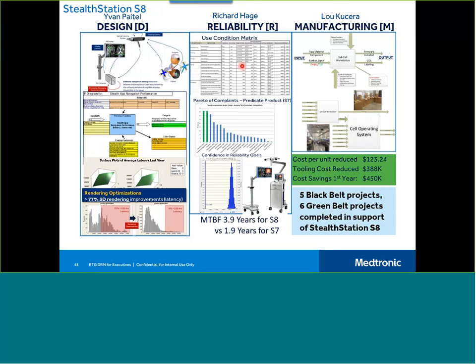On the reliability side, we did a use condition matrix and tried to look at all the ways this product could be used or misused or abused or whatever else, and also looked at complaints on the predicate product, StealthStation S7, and basically used it to optimize reliability. And as a result of that, the predicate product, StealthStation S7, had a mean time between failures of 1.9 years. We essentially doubled it to 3.9 years with StealthStation S8.